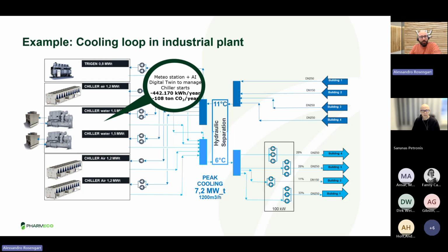During the summer, in the south of Italy, the plant experiences very hot weather with more than 40 degrees C during the day. So they need to power up all the plants to have enough cold power to keep the facility running. The point is these are huge chillers with a long ramp of startup, so the approach was, for the whole month of August, keep everything on and possibly work outside of the set point just to keep the plant operating and available.